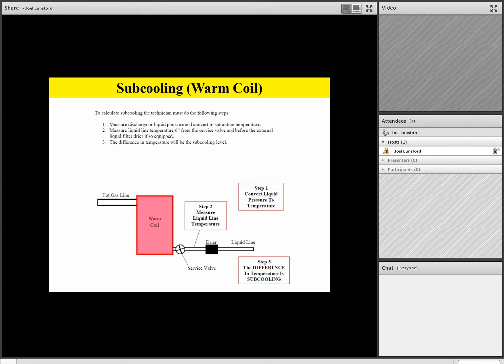Now, to measure subcooling, we're going to, number 1, convert liquid pressure to temperature off of our pressure temperature chart. Step number 2, we're going to physically measure the liquid line temperature. And then step number 3, we'll find the difference. And the difference is your subcooling level. Now remember, team, if the subcooling is high, a big number, that coil is flooded. If the subcooling is a low number, that will indicate a starved coil.